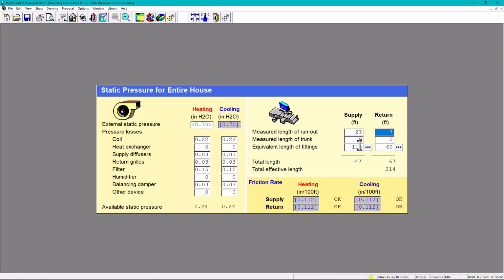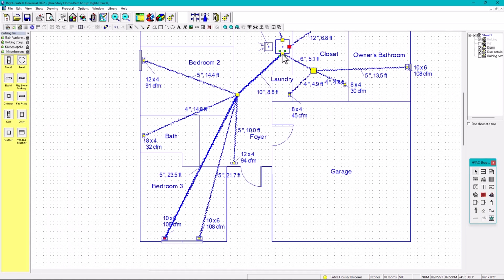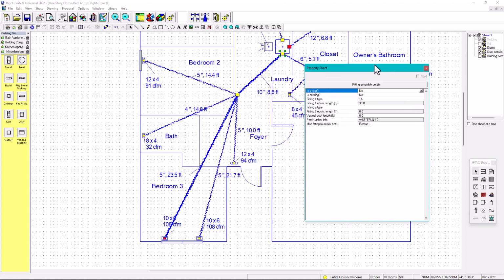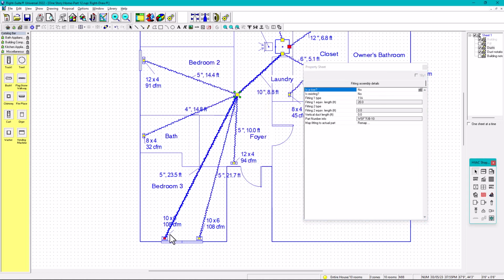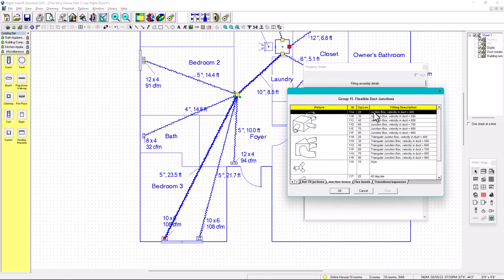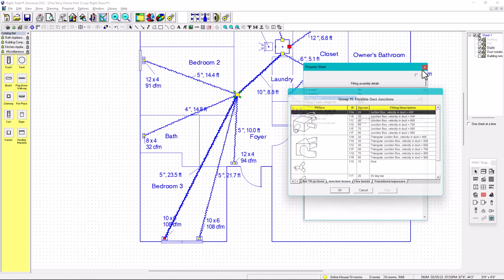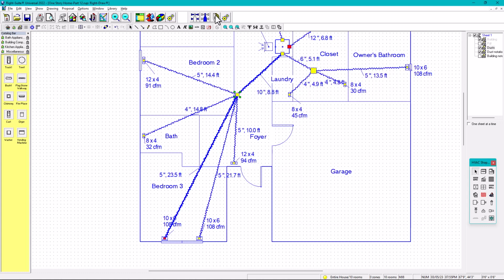So now, as you can see, we lose a lot of pressure in equivalent lengths, in the fittings especially. We're going to have like 115, and then you have here, see, fitting 1, let's check, that's 35. The other one, let's check, that's 20, and the other one here, let's check, that's 60. If you add those equivalent lengths, you're going to find the total equivalent length in fittings. But now we didn't check on this one. See, this is how it looks at the distribution box in equivalent length. It's the same process like we did for the previous one.